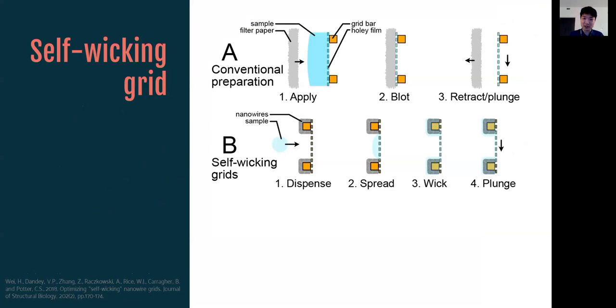So going back to the self-wicking grid. So the idea for a conventional grid, which I presented earlier, is that you have a filter paper. You press it against the excess liquid and it blots it away. And when you retract and plunge, you are left with a very thin film of liquid. For the self-wicking grids, what actually happens is that you can actually grow nanowires on the grid bars themselves, such that the grid has an innate capacity to absorb some liquid. So when you apply a sample onto the grid, this liquid is now sucked away by these nanowires and you get a very thin film. And that is the theory that is used right here in the Shake It Off and pioneered by Spotiton as well as Chameleon.